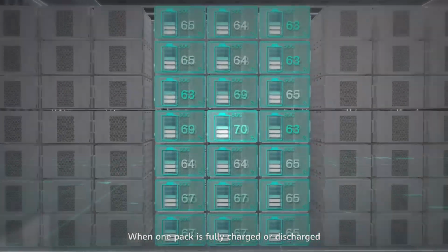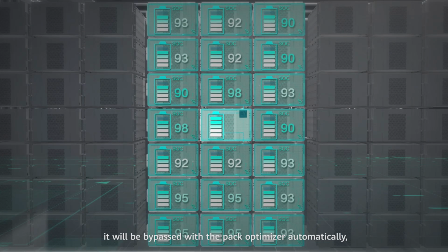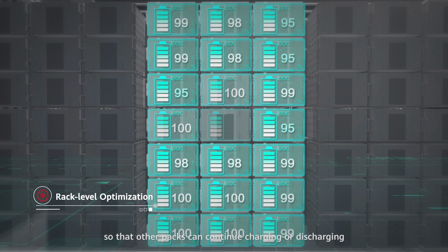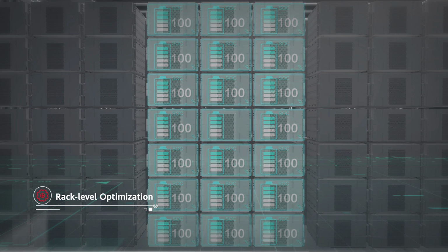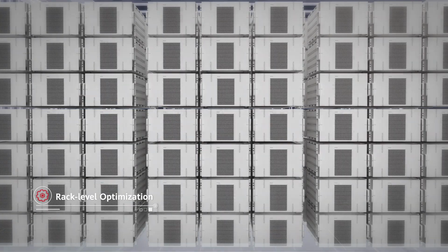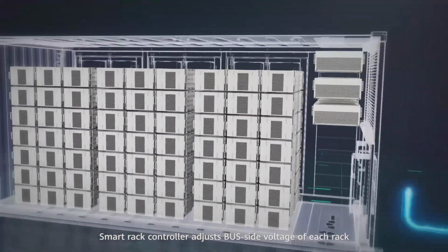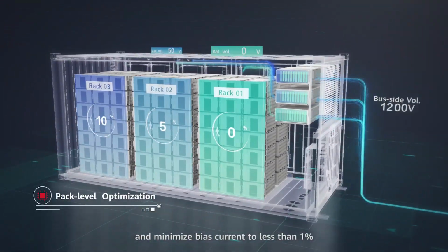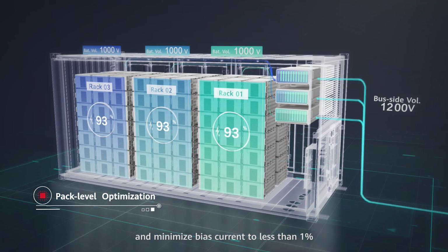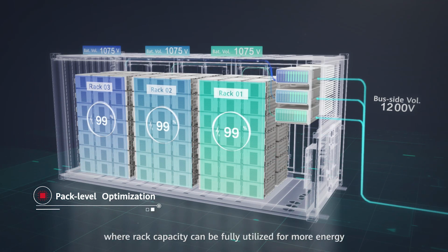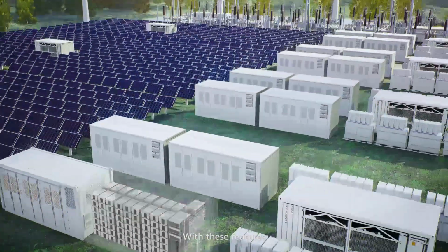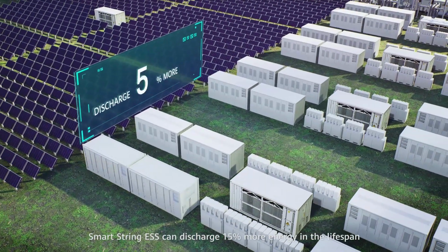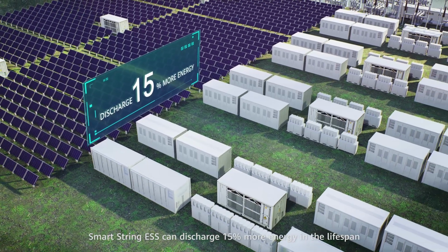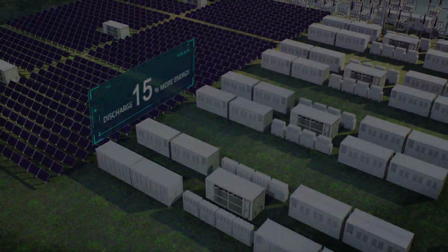When one pack is fully charged or discharged, it will be bypassed with the pack optimizer automatically, so that other packs can continue charging or discharging. Smart Rack Controller adjusts bus side voltage of each rack and minimizes bias current to less than 1%, where rack capacity can be fully utilized for more energy. With these features, SmartString ESS can discharge 15% more energy in the lifespan.